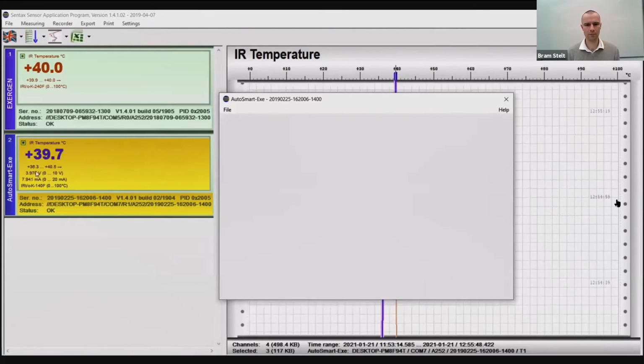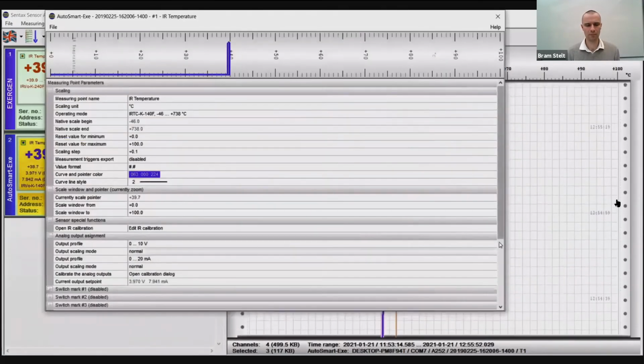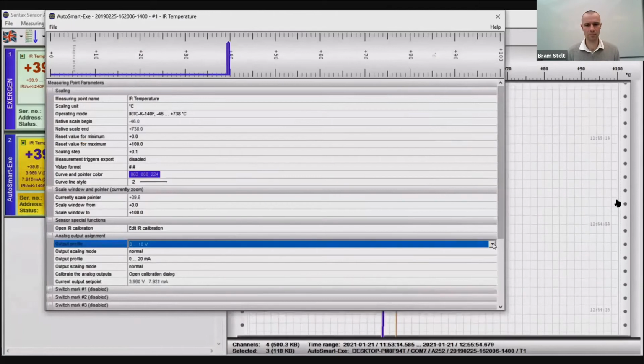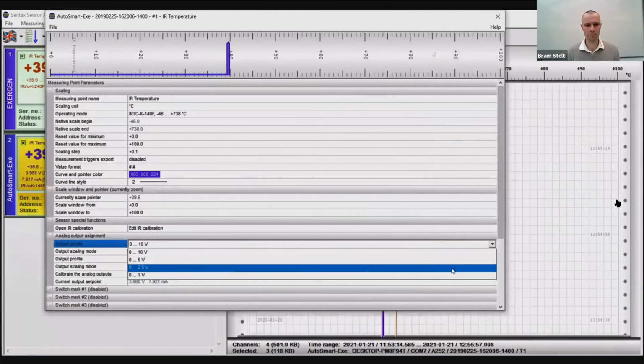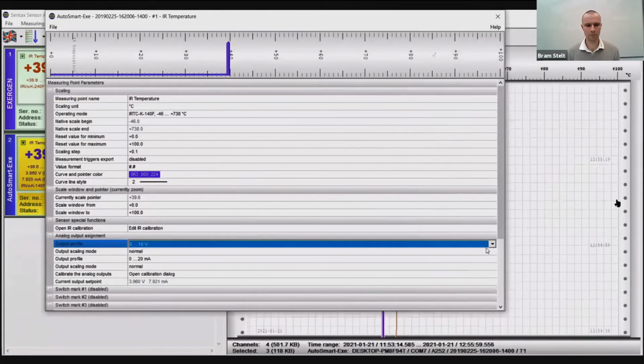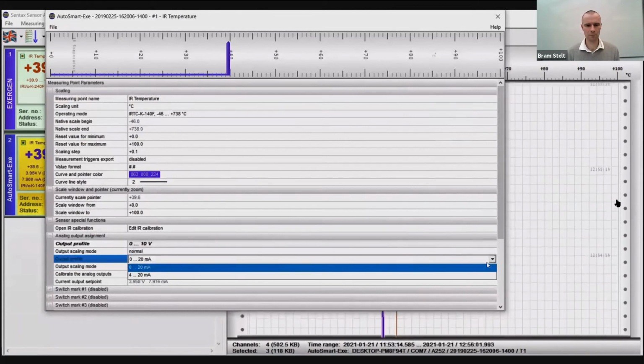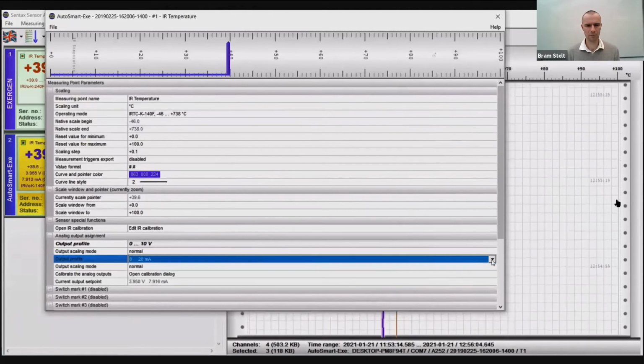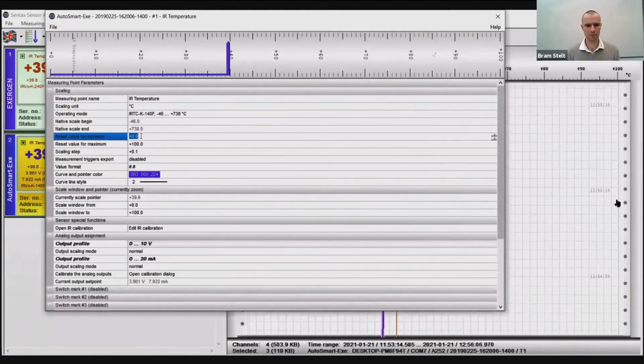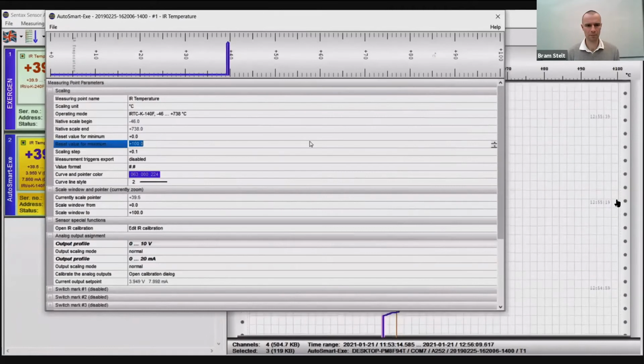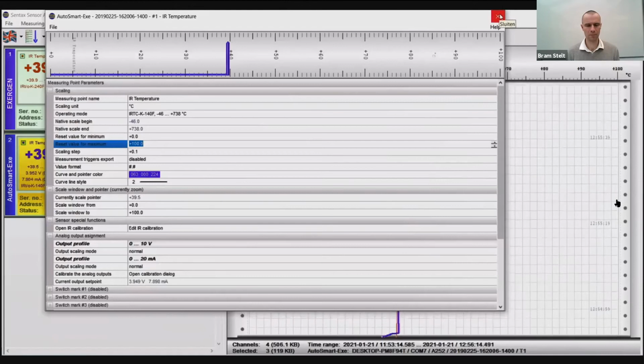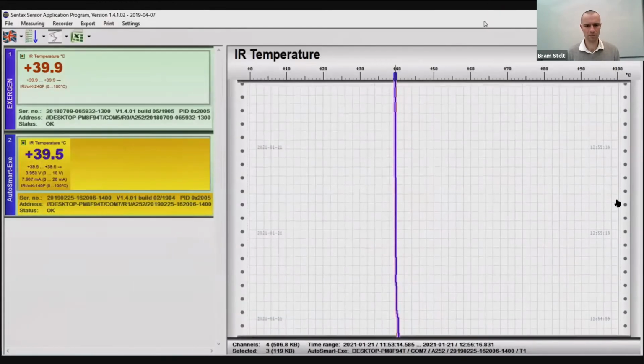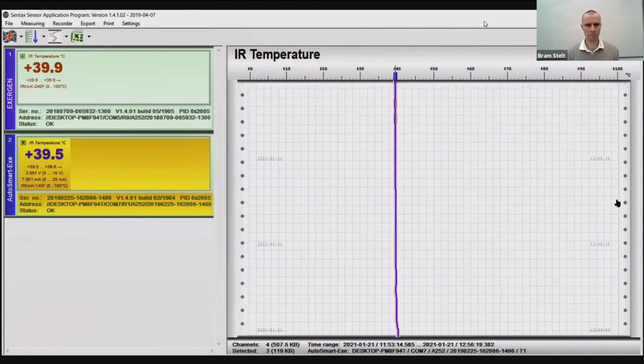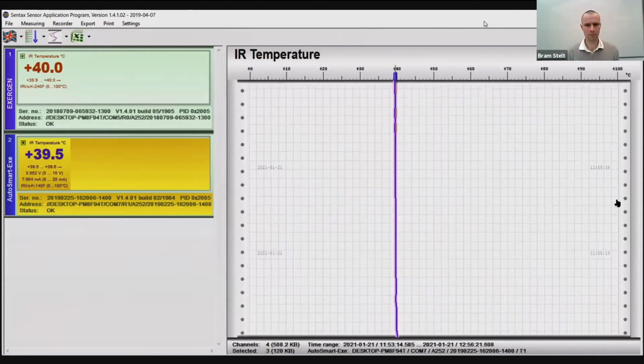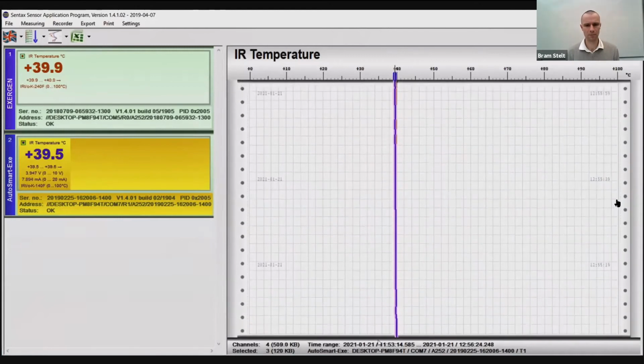What you also see in the software is that you can very easily adjust, let's say, the output. You can choose 0 to 10 volt, but you can also select 0 to 5, 0 to 2.5, 0 to 1 volt. Here you can easily select 0 to 20 milliamp or 4 to 20 milliamp. You can adjust the temperature range. So this is all very easy and very convenient to do a custom calibration. And again, as long as the application and the process is reproducible, the sensor will give you reproducible results.